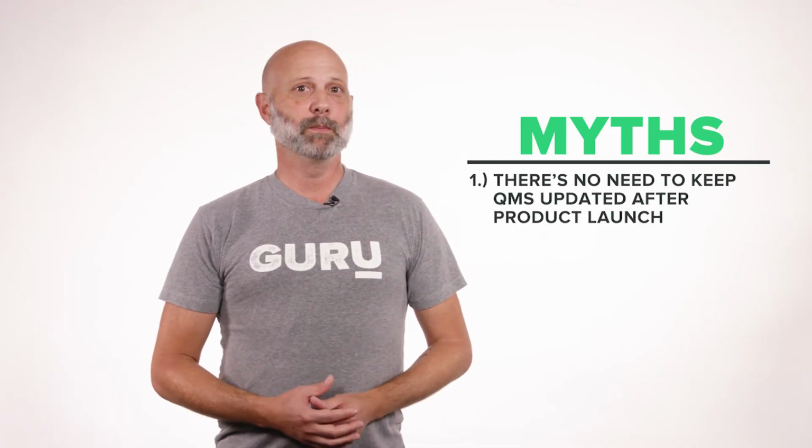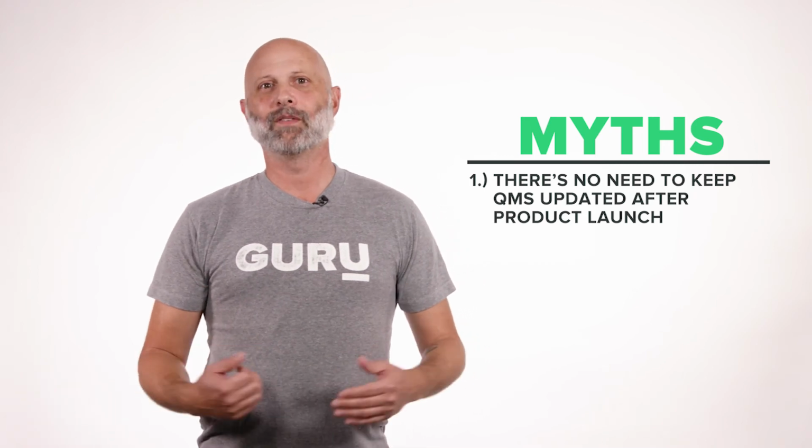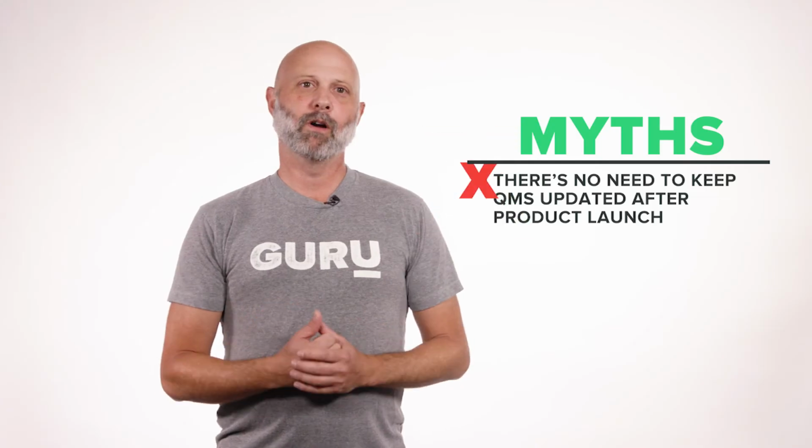One common myth that I hear during the track phase is this: once a product is launched and QMS is implemented, you don't have to worry about updating your QMS unless there is an issue identified during an ISO audit or FDA inspection. Yeah, that's wrong. The reality is, if issues are identified during ISO audits or FDA inspections, yeah, you will need to take appropriate actions. And really, that's kind of the worst time to find these things out. The whole purpose of this phase is to identify issues and areas of concerns prior to these FDA inspections and ISO audits. When done properly, your tracking activities, including internal audits, will be considered world-class to any auditor or inspector.